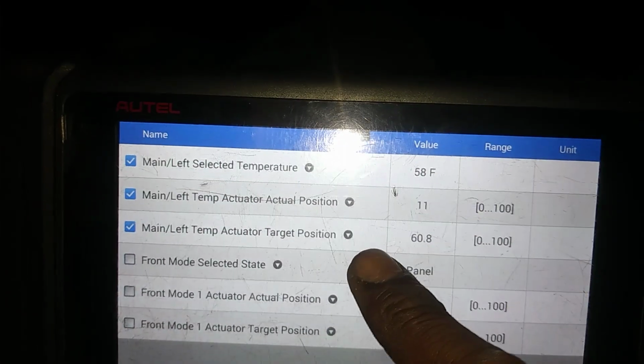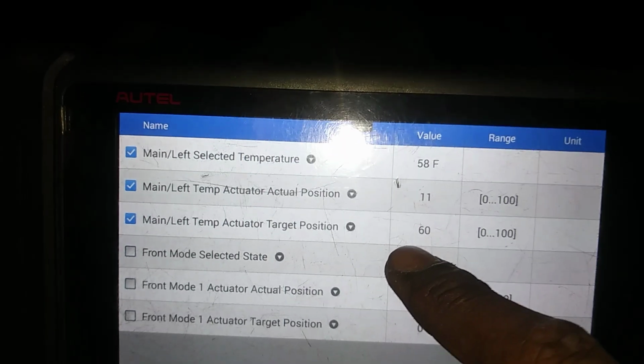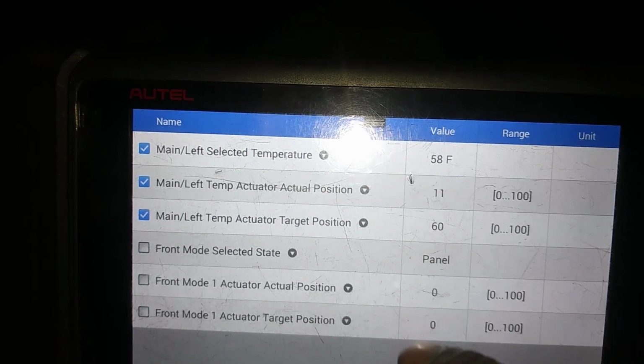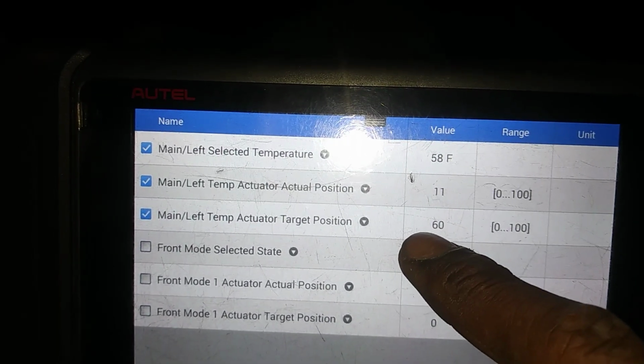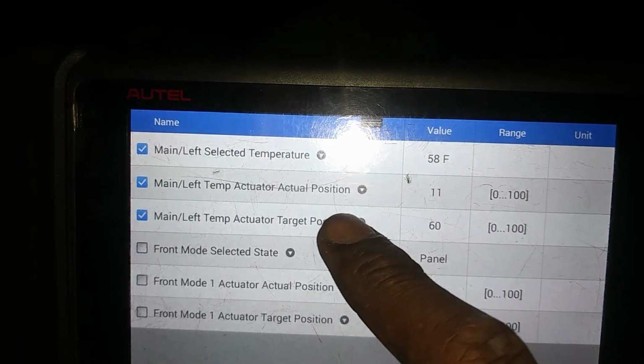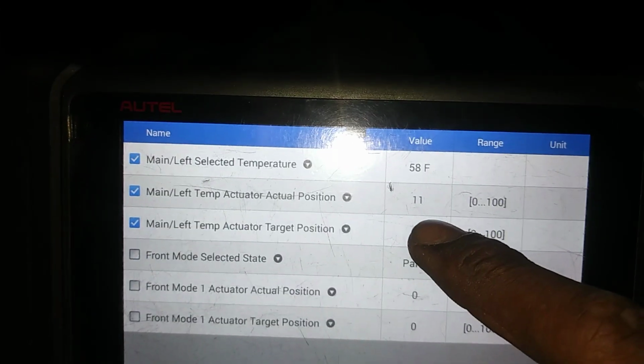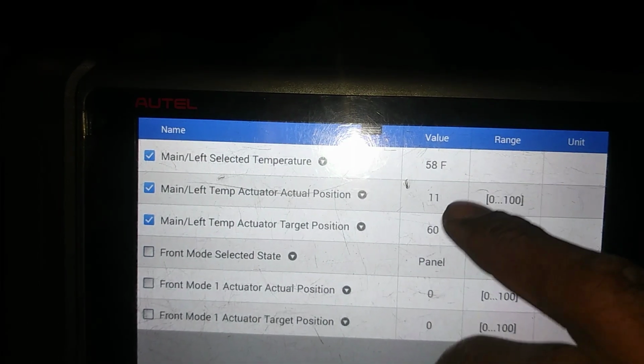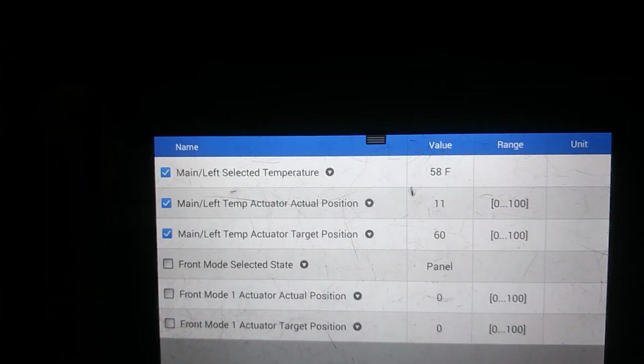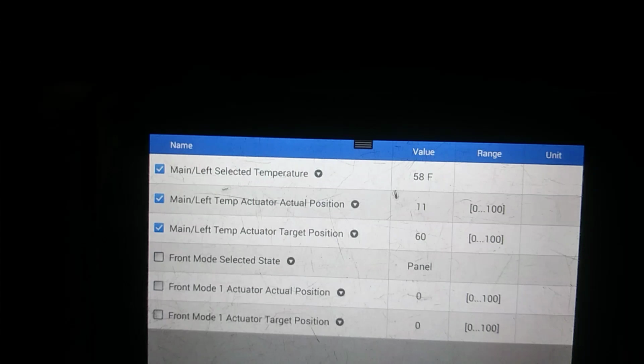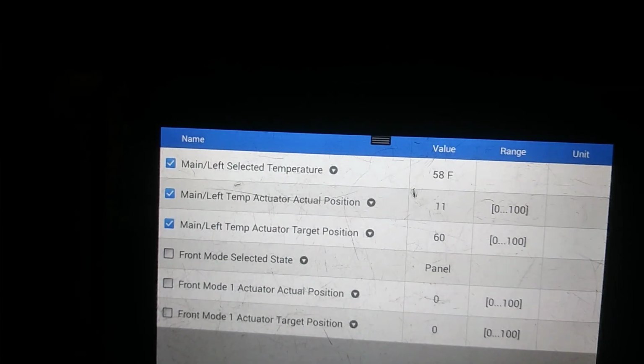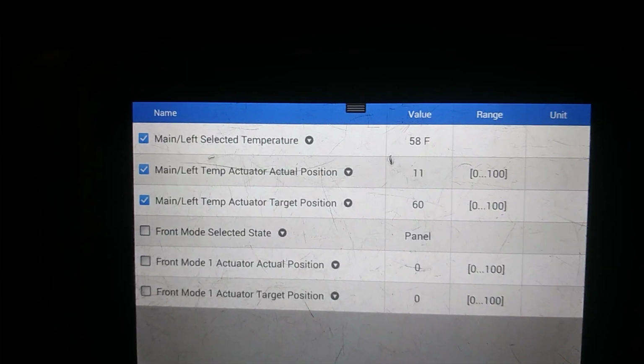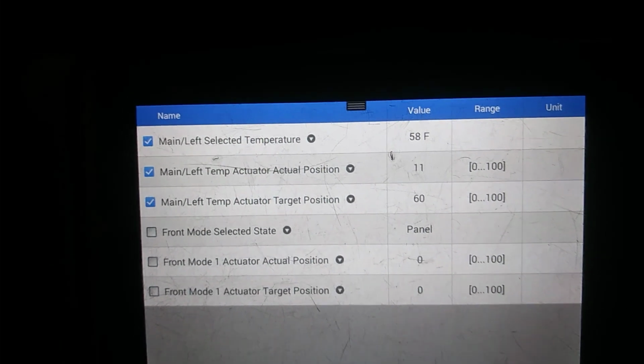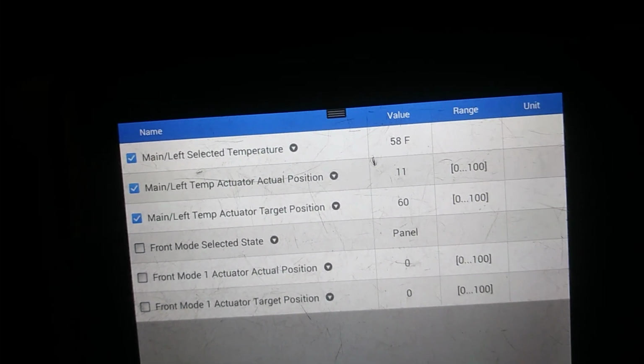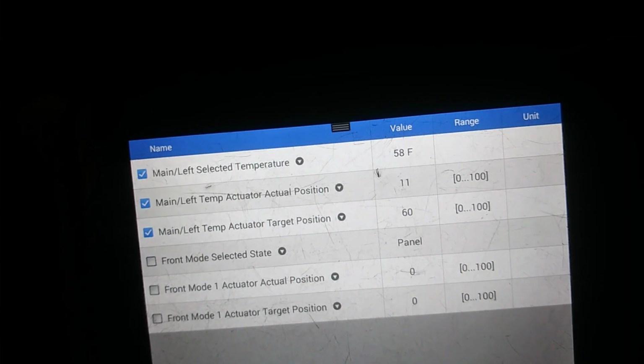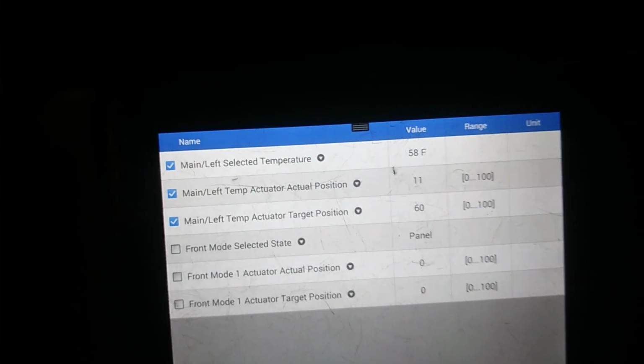Alright, so now it seemed to be more reflective of degrees versus percentage like the other one, but it's at 60 degrees now, and the actual position is not reflective by any means. So what that tells me is that there's signal going out to request it, but there's no action from the component or the part itself to actuate, move, or provide its output back to the module here.